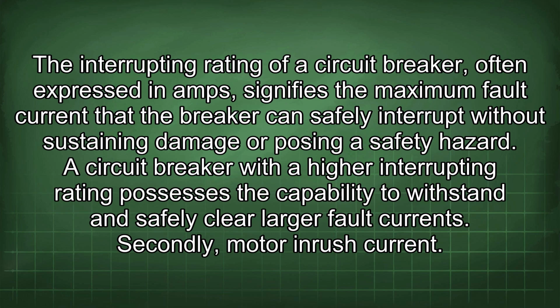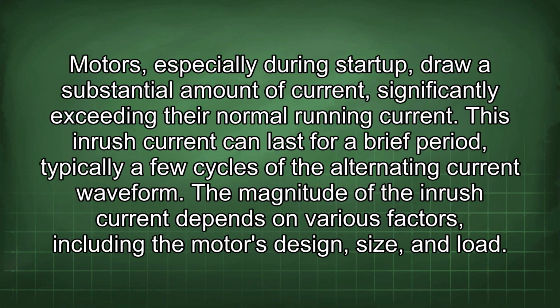Secondly, motor inrush current. Motors, especially during startup, draw a substantial amount of current, significantly exceeding their normal running current. This inrush current can last for a brief period, typically a few cycles of the alternating current waveform. The magnitude of the inrush current depends on various factors, including the motor's design, size, and load.